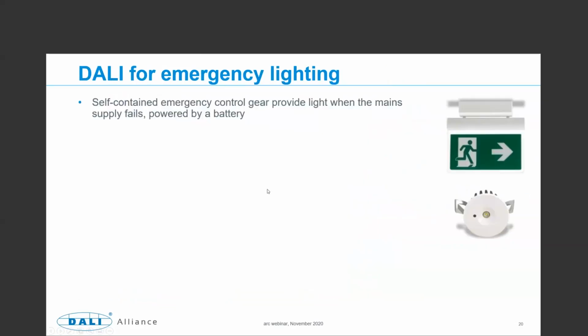And lastly, before we hand over to Paul, let's have a quick look at emergency lighting. This is another key driver for using DALI for lighting control. DALI provides self-contained emergency control gear, which have one main function: to provide light when the main supply fails. And the light output, the driver, is then powered by a battery. Self-contained means the driver battery arrangement is in the control gear or right next to it, attached to it. Central battery is the other type of emergency. We do have a standard for that as well.